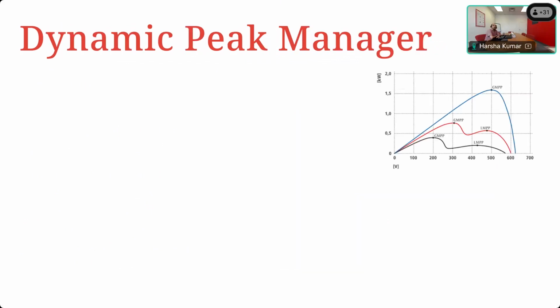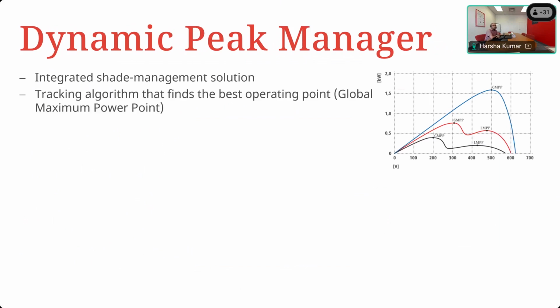Now, outside of that, this is a dynamic peak manager. The reason I'm bringing this up is oftentimes, especially when people try to sell you optimizers and microelectronics and say you don't need to increase the number of panels, you can throw this piece of electronics behind it and get more juice from the same PV array, I'm not going to deny that, but what I'd pitch to you is the failure rate on the electronics used to get more juice out of the same panel is much higher than the failure rate of the panel. Also, your panel is very robust and the price on it is always going down, at least for now. So if you've got the roof space, you'd rather throw on more panels than more failure-prone electronics to get more juice out of the same PV array. Which is why we always suggest maximizing that.